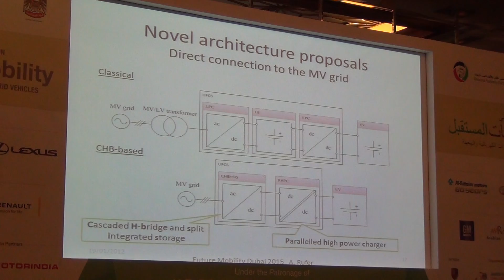When we looked at this topology, the system uses a series of modules. The nature of the module, the topology of one H-bridge module, is represented here. By combining series connections of such modules, you can benefit from what we define as a multi-level waveform that has a very low harmonic content. This is a big advantage when interfacing to the grid with that kind of system.